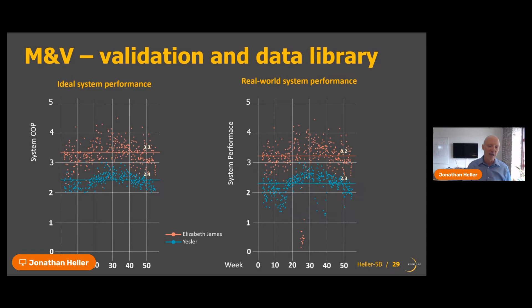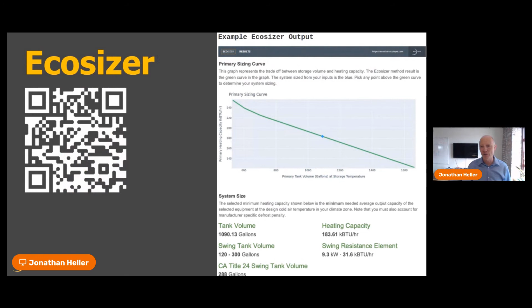Another key tool we've developed over the last couple of years to support the industry is the EcoSizer program, which shifts the focus for designers on sizing these systems from reliance on high capacity and low storage volume—typical for gas systems—to much more reliance on high storage volume with enough heat pump capacity so the heat pumps run between 12 and 16 or 18 hours per day. This is the most economical way to provide these systems and also allows for the most load shift capability.